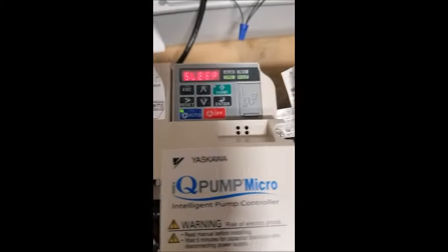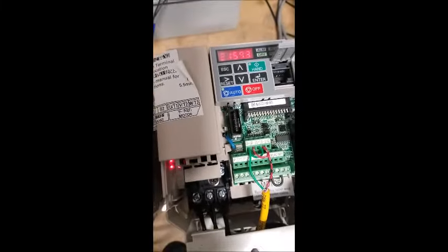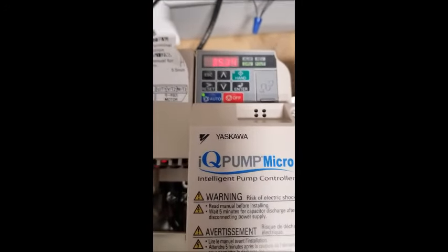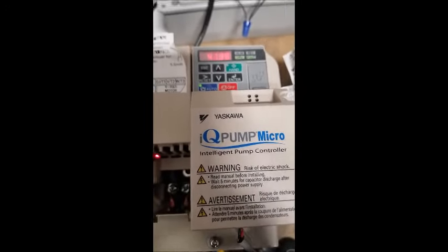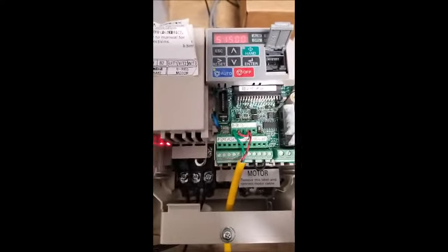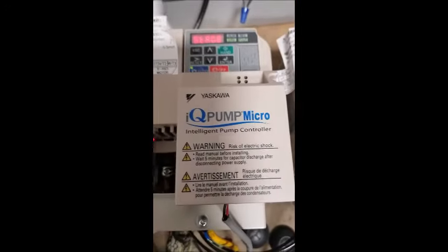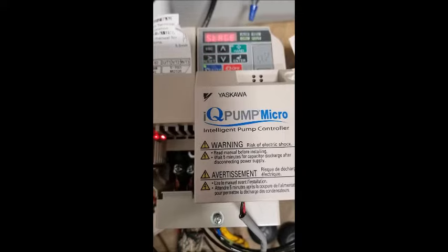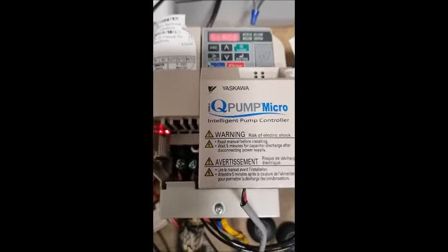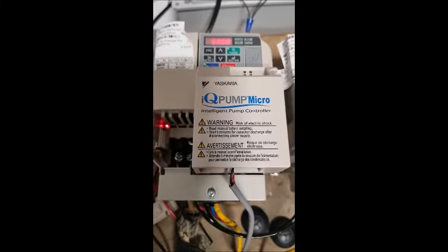And if the pressure were to drop, the drive wakes up, and the whole thing starts over again. Another great feature of this setup is it automatically will pick a lead drive that has the lowest runtime. So any one of these drives can become the lead at any time based on the lowest runtime. This leads to a redundant system.